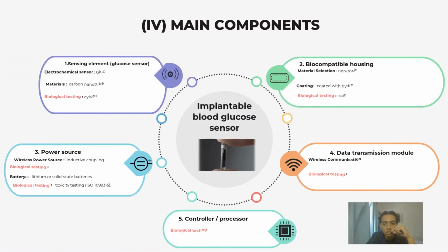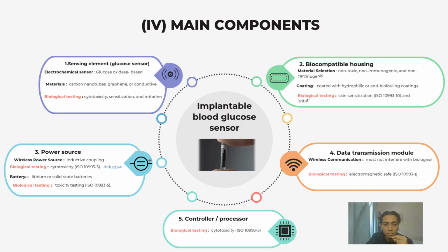So for the next part, I will explain the main components of the implantable blood glucose sensor. Basically, there are 5 main components of this biosensor. The first one is the sensing element, which is the glucose sensor. It is usually an electrochemical sensor of the glucose oxidase type, and the materials used for this component are usually carbon nanotubes, graphene or conductive polymers. This material must undergo biological testing of cytotoxicity, sensitization and irritation according to ISO 10993-5 and ISO 10993-10.